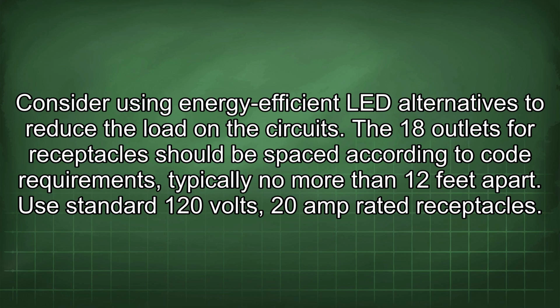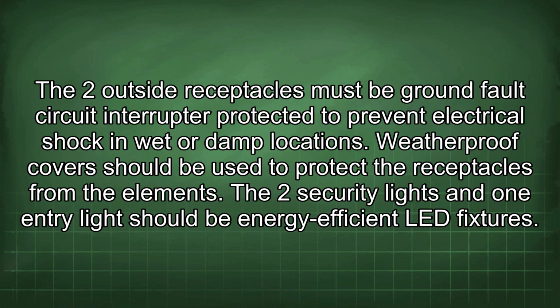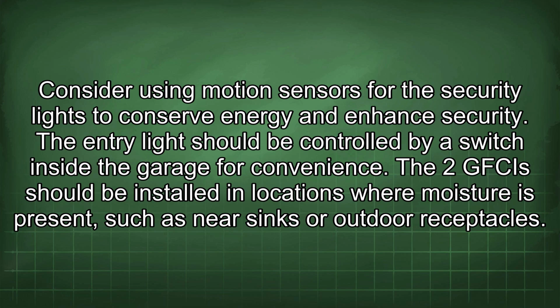The 18 outlets for receptacles should be spaced according to code requirements, typically no more than 12 feet apart. Use standard 120 volt, 20 amp rated receptacles. The two outside receptacles must be ground fault circuit interrupter protected to prevent electrical shock in wet or damp locations. Weatherproof covers should be used to protect the receptacles from the elements. The two security lights and one entry light should be energy-efficient LED fixtures. Consider using motion sensors for the security lights to conserve energy and enhance security. The entry light should be controlled by a switch inside the garage for convenience.